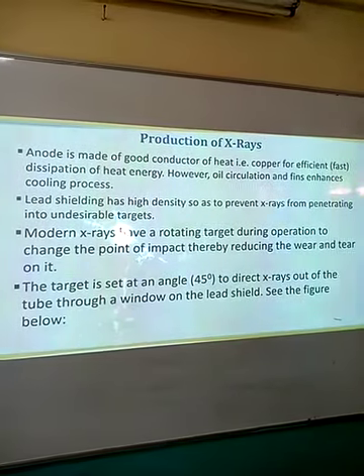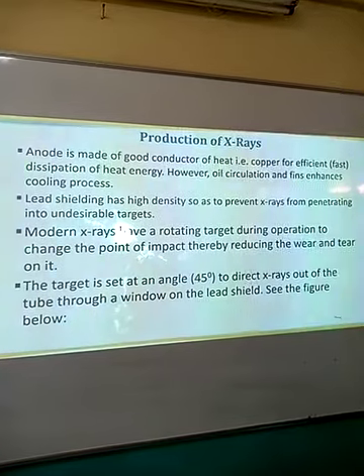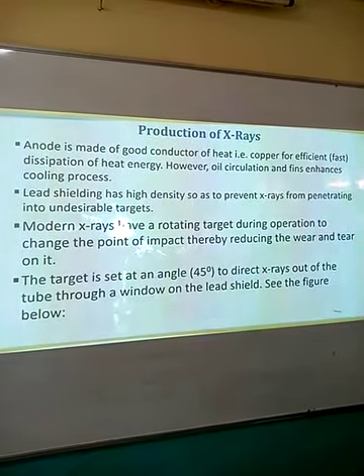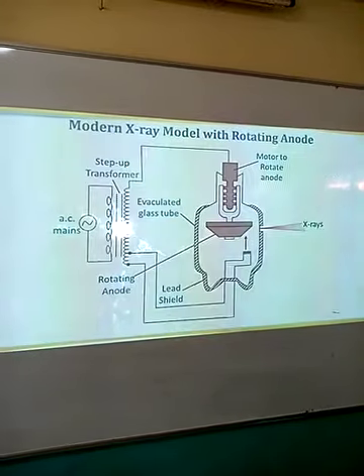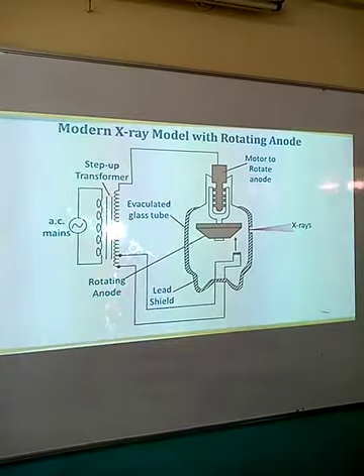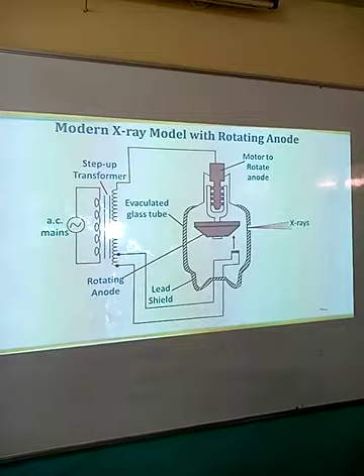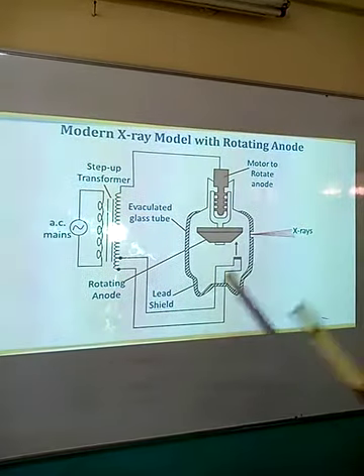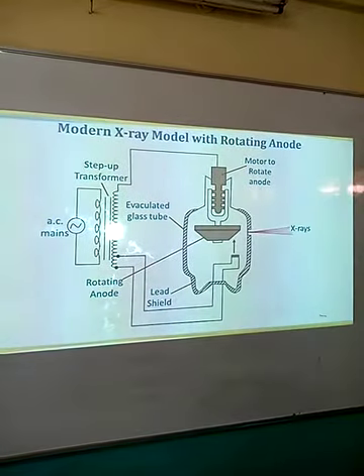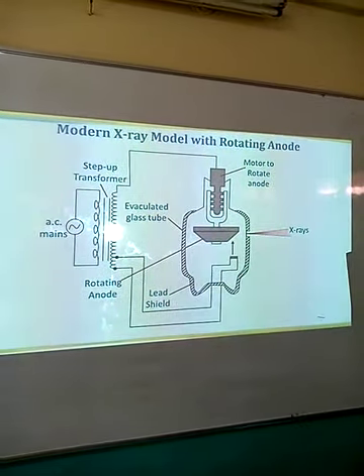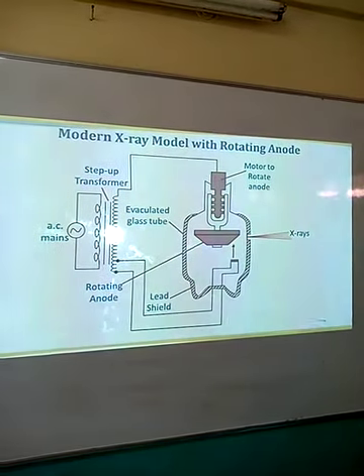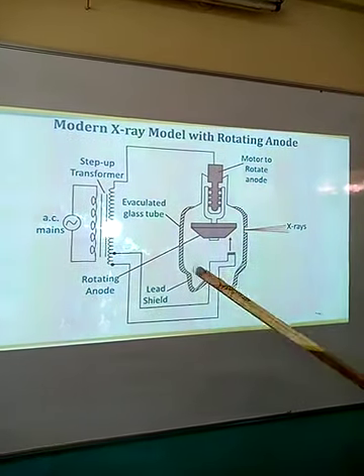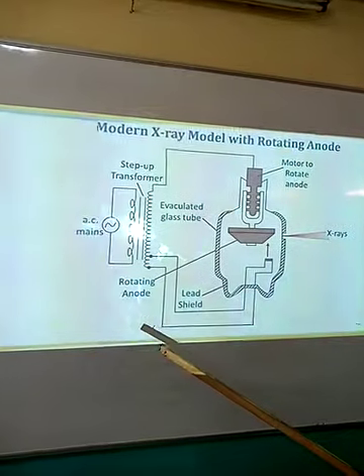The X-ray tube has undergone some evolution. We now have a modern X-ray tube with minor modifications from the original. In this modern X-ray tube, the anode is made up of a rotating material — it rotates, connected to a motor. As the electrons produced from the cathode hit the anode, the anode rotates. It is supposed to change the point of impact, and the purpose of changing the point of impact is to reduce the wear and tear at the anode. These are the parts or features of the new X-ray tube.